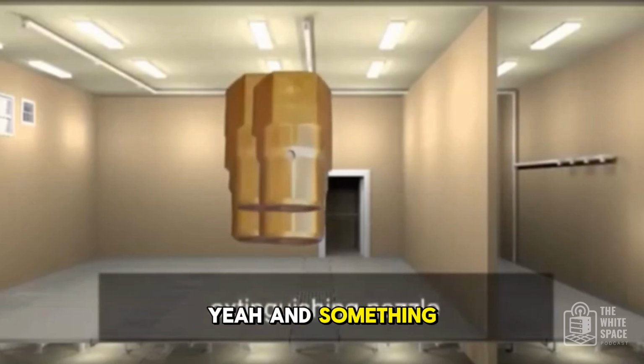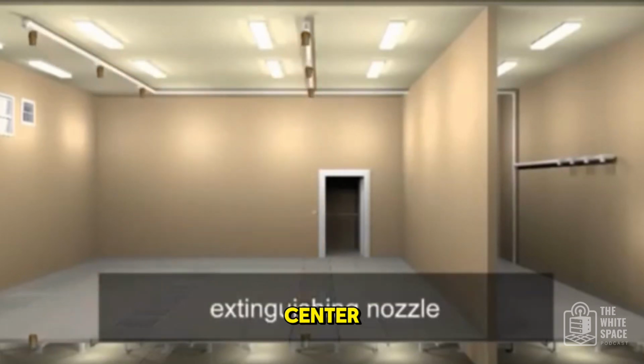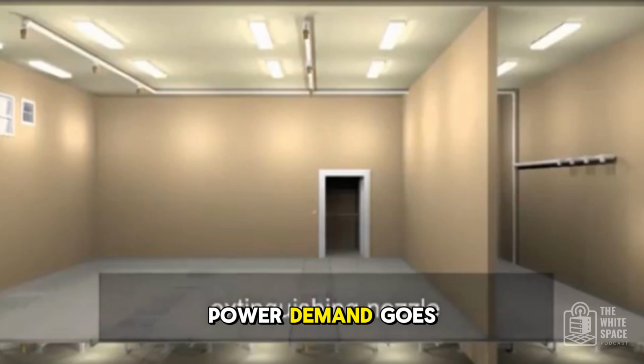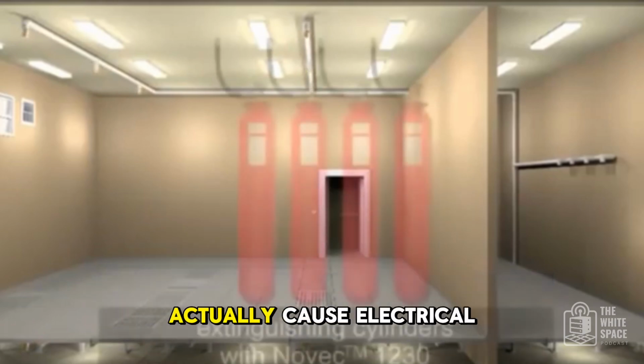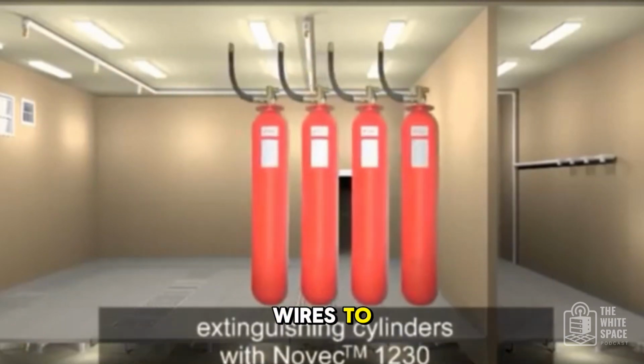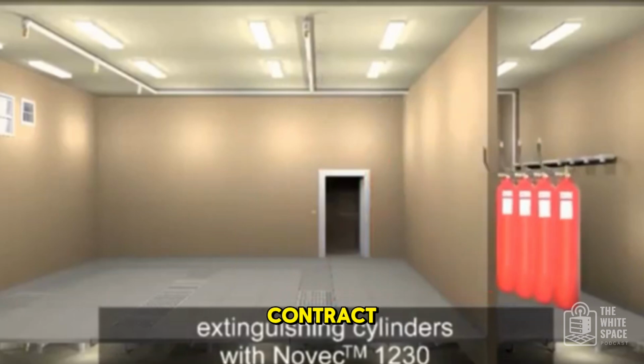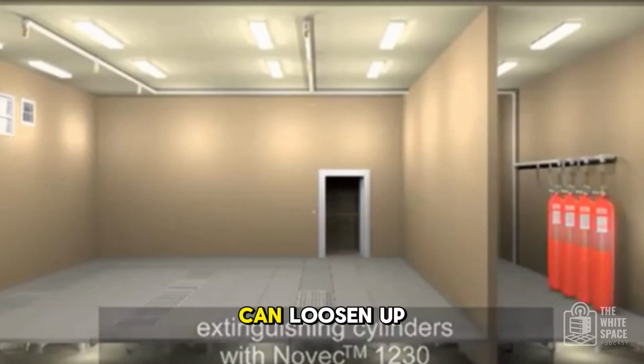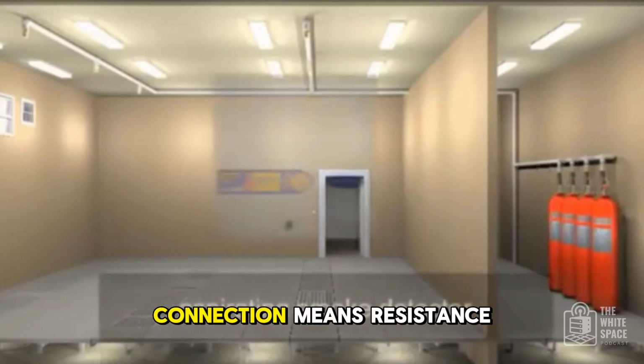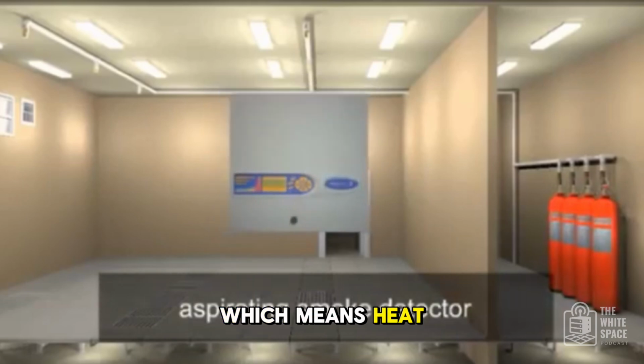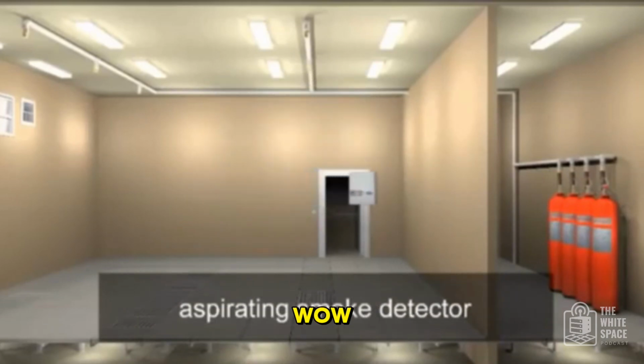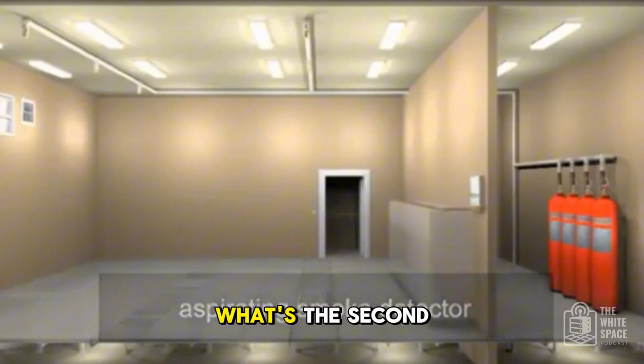Sometimes, yeah. And something interesting, the IT load in a data center fluctuates, right? Power demand goes up and down. Sure. That can actually cause electrical wires to physically expand and contract. Over time, connections can loosen up. I see. And a loose connection means resistance, which means heat, potentially a fire. Wow, okay. That's subtle. What's the second bucket?